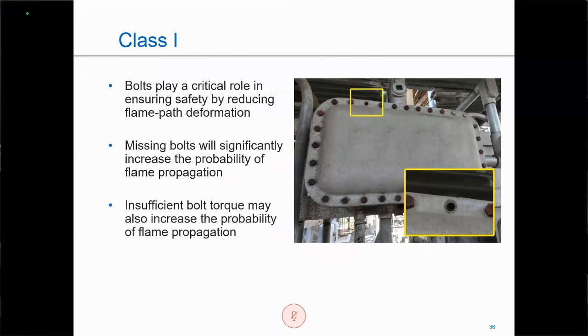So as you can see here, it's also extremely important if a bolt is broken or missing to replace it. Now, some manufacturers have captive bolts, so this isn't quite as much of an issue. But for the manufacturers that don't have captive bolts, it's very common for the person working on the unit to take out all the bolts and lay them on the ground. So if one were to become missing, it's important to contact that manufacturer to have it replaced.